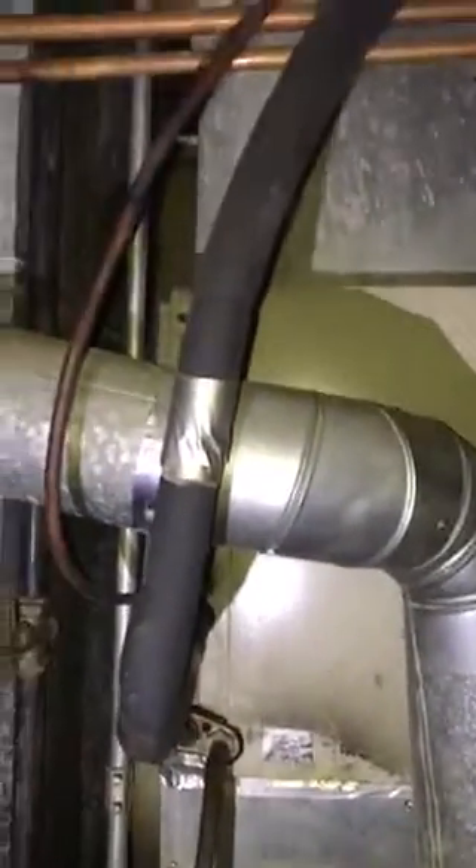All the fire rating has been removed from the ceiling — I'm not sure why, but it all needs to be put back, probably because of water leaks from upstairs. We may not pass inspection as a result. It looks like there are fire dampers inside, but the drywall doesn't go all the way up, and drywall patching would have to be done by somebody else.